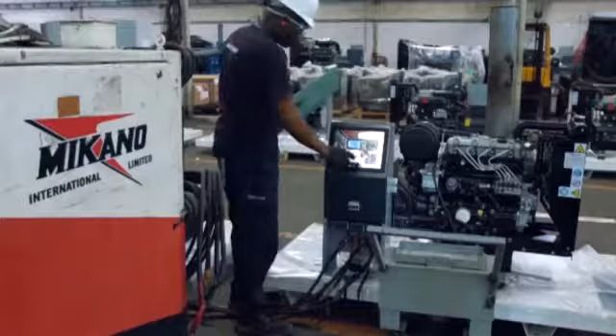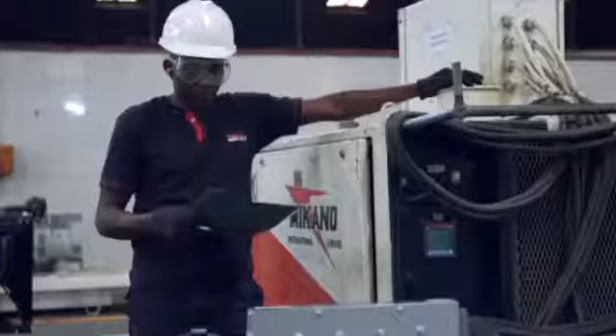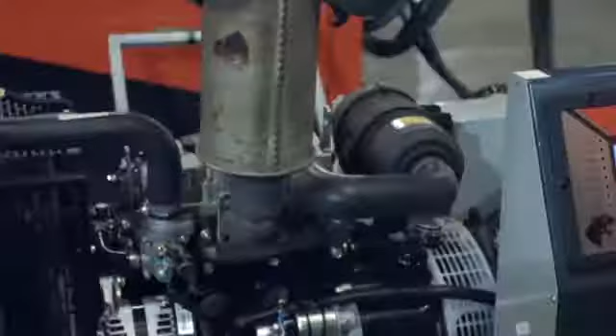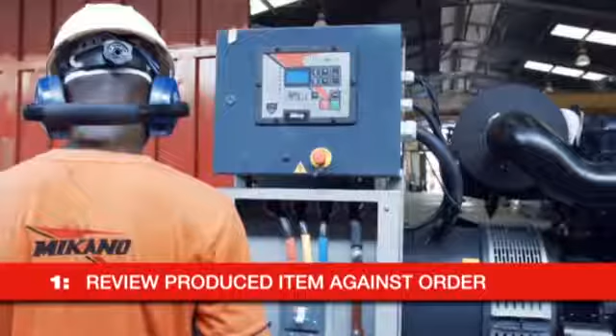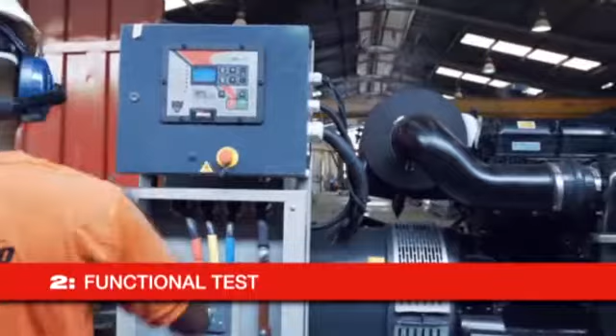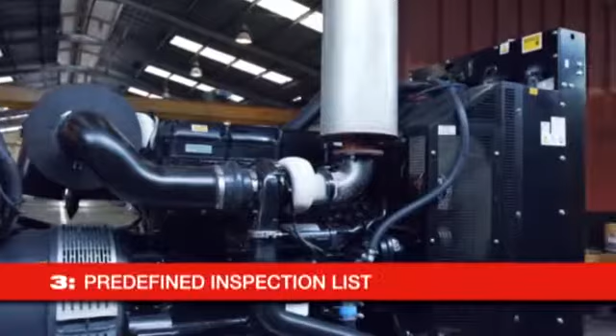After the components are assembled, the product is sent for a 1-hour quality check, testing its full load between 20% and 110%, after which it would be considered a finished good if it shows no defaults. MIKANO maintains a very strict quality control procedure split between 2 inspections called quality assurance and quality control. The quality control process has a 3-stage process: first, reviewing the specification of the produced item against the production order; second, functional test using simulations and load banks to ensure full function, covering 90% of the process; and third, a predefined inspection list. The assembly is staffed with about 100 professionals and specialists, including some of Nigeria's finest mechanical and electrical engineers.